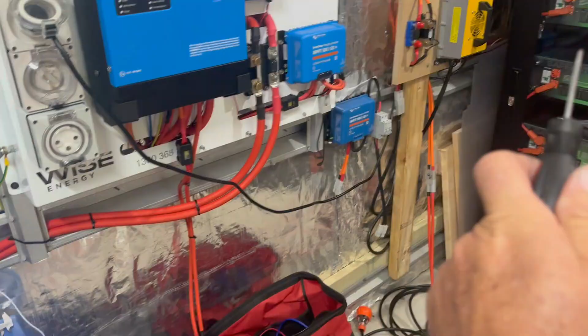The other thing I'm going to do is keep the load on very high throughout most of the test, and then for the last 5 minutes or so, when it gets down to say 5% capacity, I'm going to disconnect that battery charger and put a smaller load on it. That'll allow me to pull a little bit more out of it. It doesn't make a lot of difference with lithium, but it's going to make a little bit of difference, and I really want to see what I can get out of this battery.